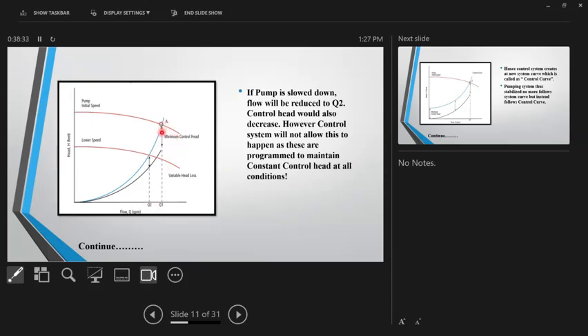Here you will see this component, control head, has reduced, right? Now this is not allowed, because we just said this control head is independent of the flow. If the pump is slowed down, flow will reduce to Q2, and control head would also decrease. You can see that from the shape of the curve. Here it was this much, now it is this much. However, the control system will not allow this to happen, because the fundamental is that the control head will always be constant, irrespective of the flow. We always program the pump speed control to keep the delta P setting the same. So what we feel logically should happen is not making sense to the control system, correct?